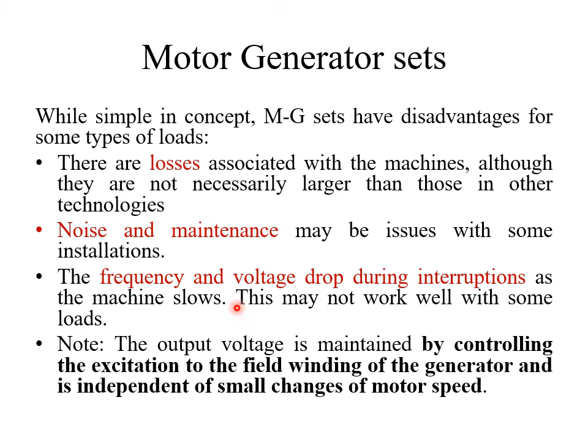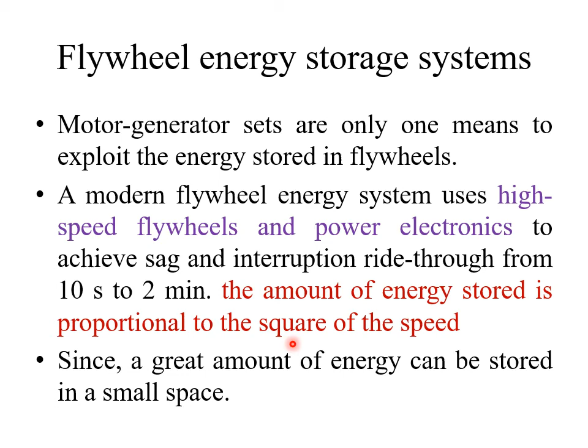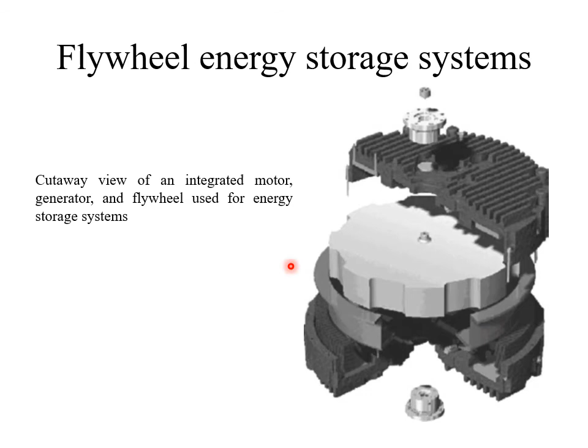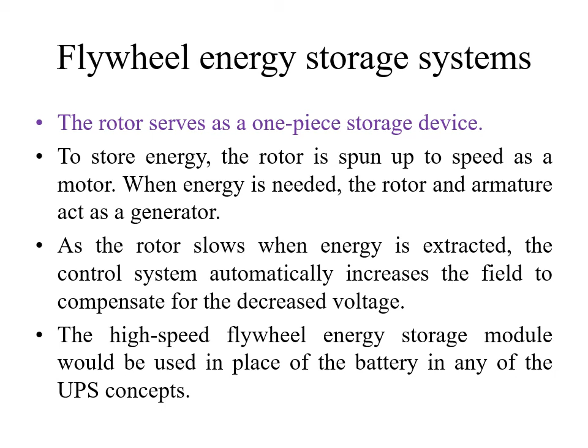The flywheel energy storage system also provides a better solution for voltage sag. The modern flywheel, which uses high-speed flywheels with a power electronic system, is able to provide solutions for this voltage sag. In this case, the amount of energy stored is proportional to the square of the speed. This is the cutaway view of an integrated motor, generator, and flywheel used for an energy storage system. In this system, the rotor serves as the storage device.